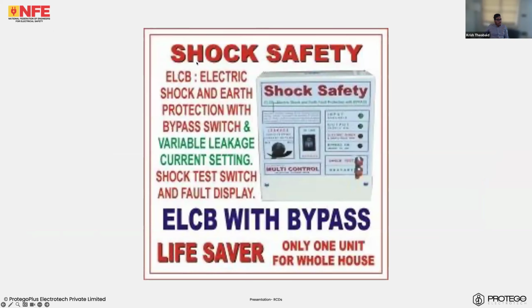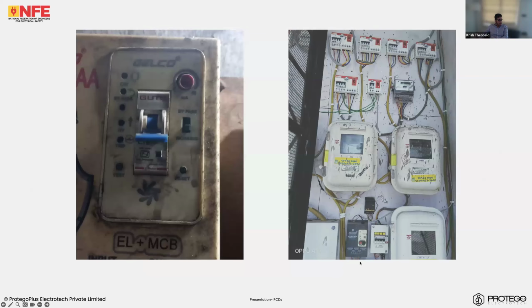So next time you see a poster like this, shock safety, ELCB, electric shock and earth protection with bypass switch, please realize that this is extremely non-standard. Firstly, ELCB is no longer available in the market. Secondly, how can you have an ELCB with a bypass switch? Because the bypass switch defeats the very purpose of the device. And only one unit for a whole house. You will see how this is complete nonsense.